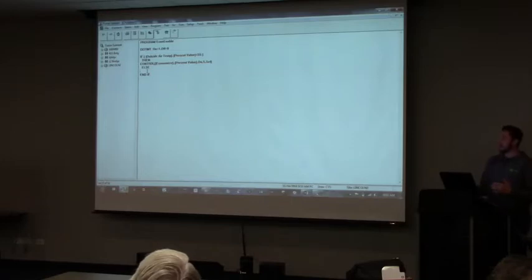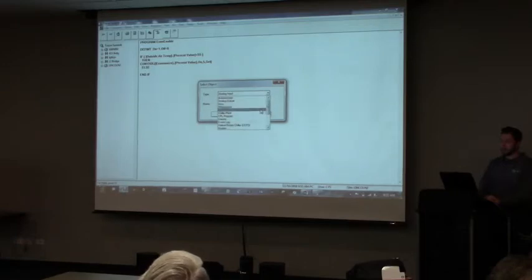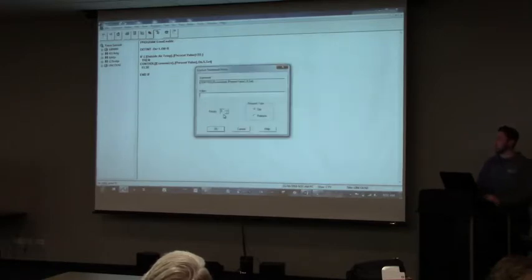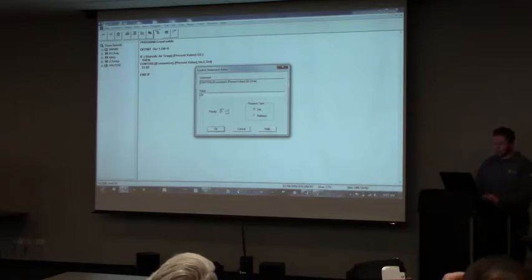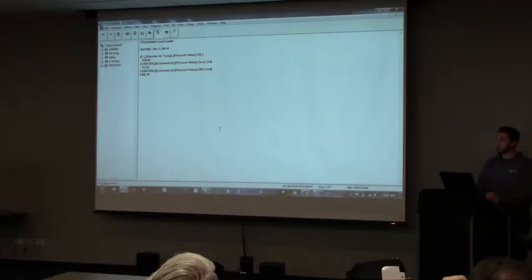And then pretty much else, if that's not true, you just want to control it off. So I'm just gonna go right back up to Edit, and then hit add statement and control, and then go right underneath here, go back to binary outputs, economizer, and then it's gonna say, what do you want to control the value to at a 5? And you can change the priority up and down, just so you know. And you can set it to release. I always just do set, so I can put off, and then hit OK. That implements it in there.